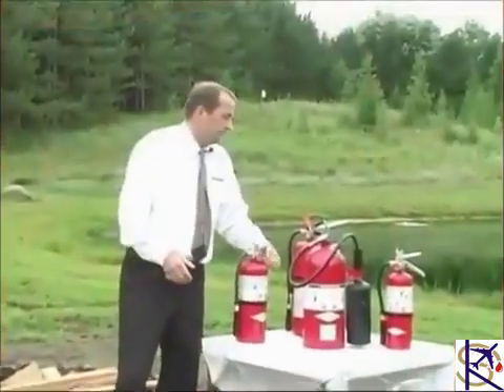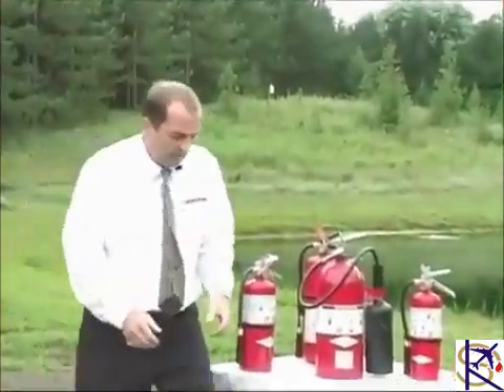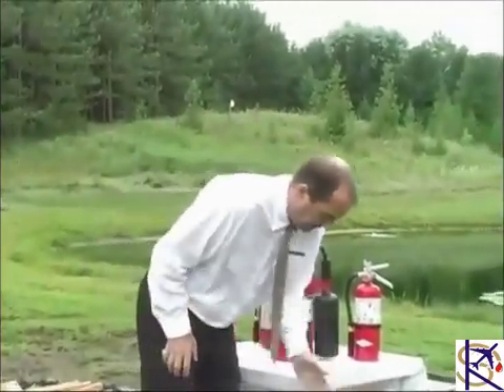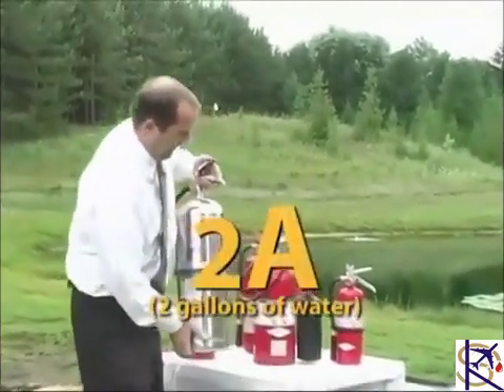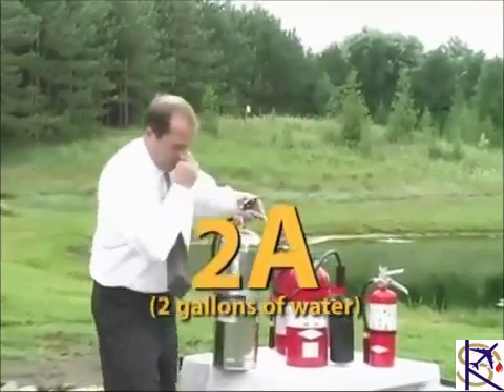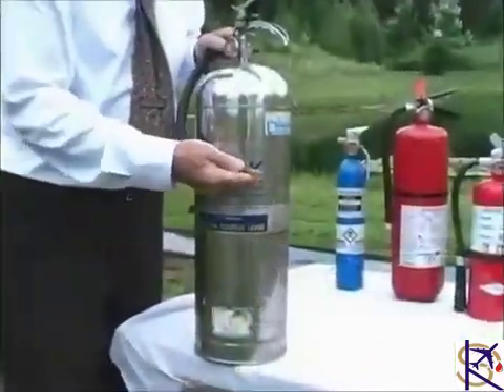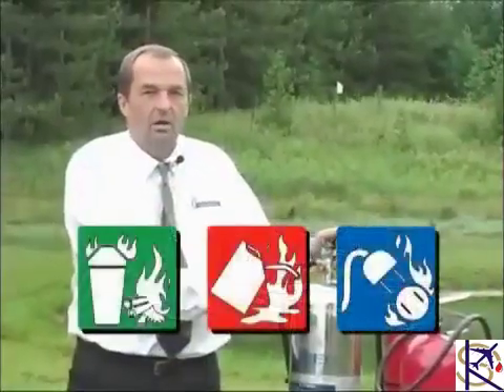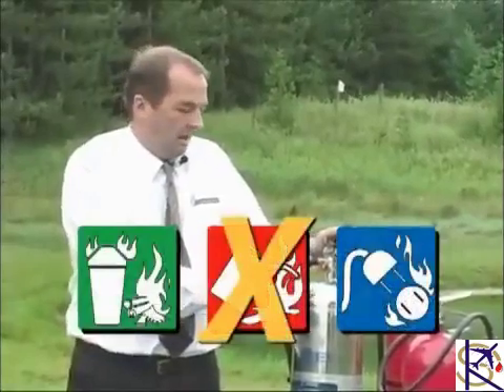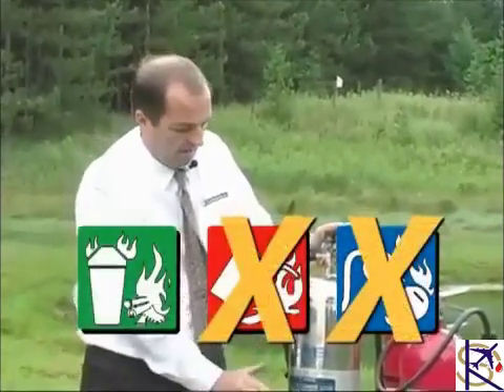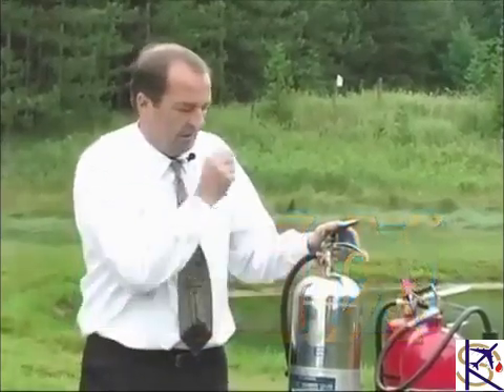Now we'll talk about a water pressure extinguisher, which is a 2A rating. That means it's 2 gallons of water. An A rating is for wood and paper. No B rating, no oil, and no C rating, simply wood and paper. 2 gallons of water, pressurized with nitrogen.